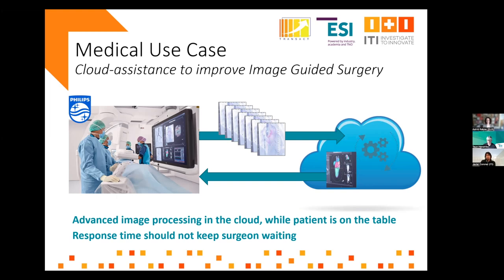This all happens while the patient is on the table and the catheter is inside the patient, so it must function. The response time should be low so that the surgeon can proceed with the operation. The amount of x-ray dose to the patient is also limited, as there is always a continuous low-dose x-ray to ensure a live image.